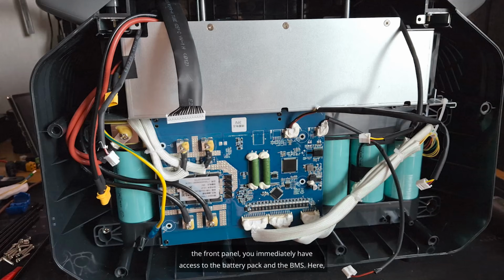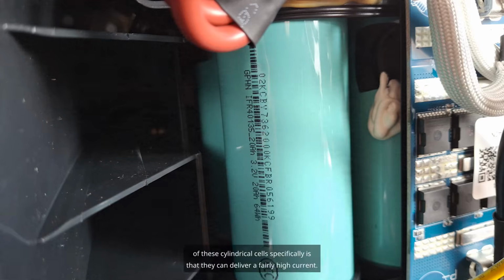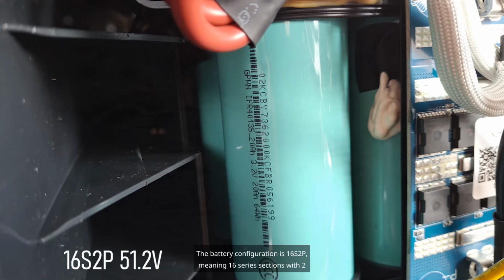As soon as you remove the front panel, you immediately have access to the battery pack and the BMS. Here, cylindrical lithium iron phosphate cells are used. A feature of these cylindrical cells specifically is that they can deliver a fairly high current. For example, this cell, with a capacity of 20 Ah, can deliver a current of up to 60 A. The battery configuration is 16S2P, meaning 16 series sections with 2 cells connected in parallel, and such a design easily withstands a load of 3.2 kilowatts.